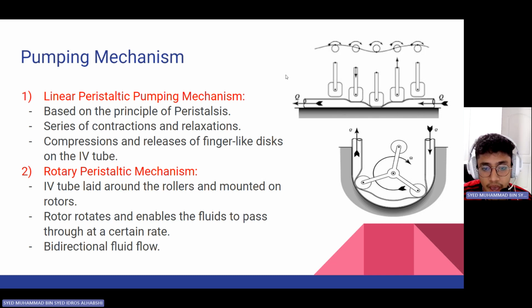As for the rotary peristaltic pumping mechanism, the IV tube is laid around the rollers and mounted on a rotor, as seen in the bottom photo on the right. As the rotor rotates, the IV tubing gets blocked and forces the fluid to flow. Depending on the rate set by the user, the motor drive will control the rotor speed accordingly. The flow direction can also be reversed, allowing bidirectional fluid flow, by changing the direction of rotation of the rotor.